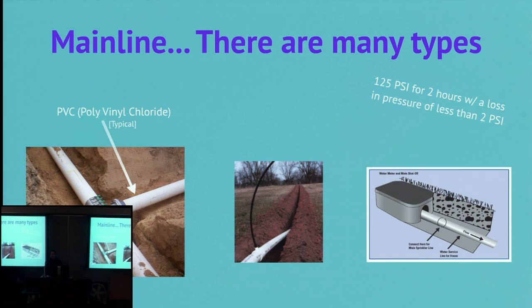And after 2 hours, if there's been no PSI loss or maybe a couple of PSI, then the main line's ready to be buried. If the pressure is less or more than 2 PSI loss, then you need to walk that main line and check all the fittings and see if something's leaking. And you write that down on your punch list, and the contractor has to go back and install the brand new fitting and not just try and use glue or a Band-Aid to try and fix that fitting from leaking.